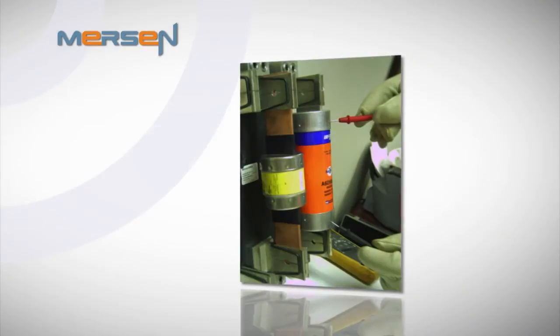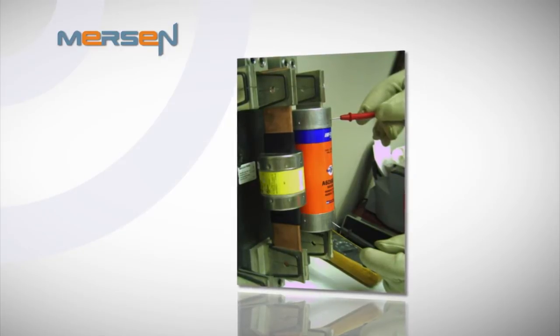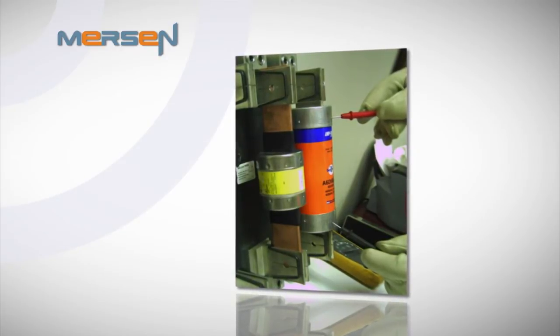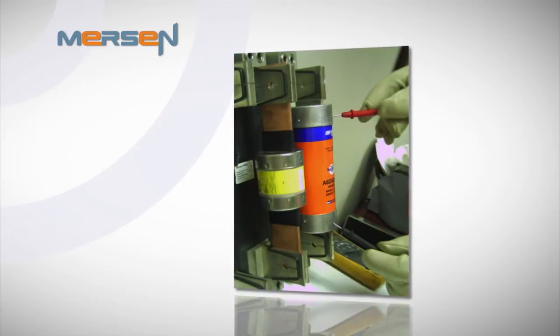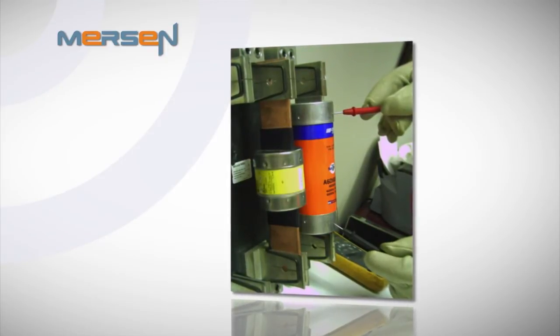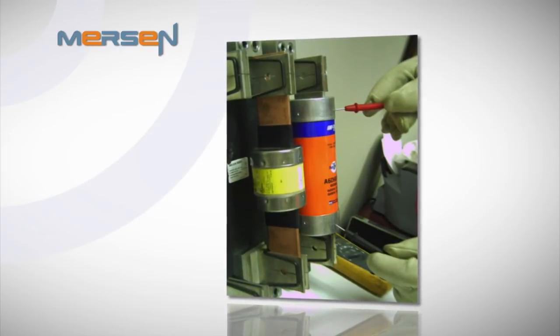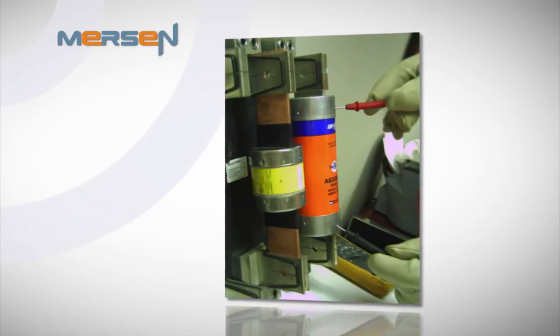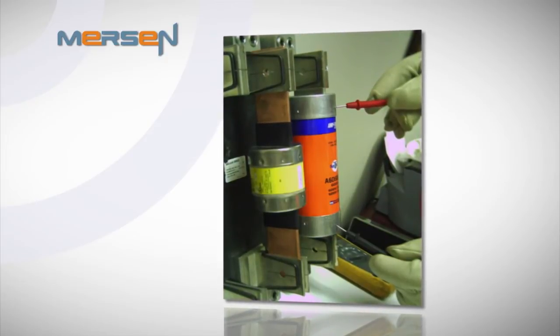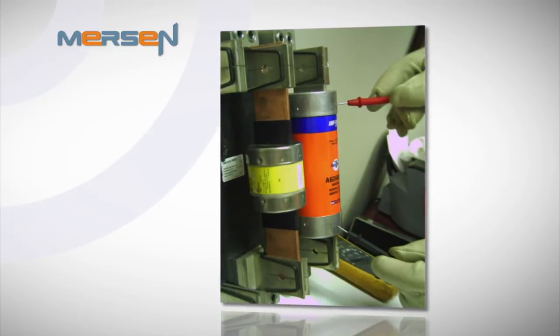An additional safety feature of Mersen's Amp-Trap 2000 fuses is the ability to test voltage with PPE to determine that they are safe. Mersen's test method keeps your people, plant, and equipment safe. OSHA requires lockout-tagout procedures that include testing for the absence of circuit voltage. Historically, people have used the fuse end caps for a convenient test location. Fuses with disconnected and insulated end caps can appear to be de-energized when they are not. As an industry leader, Mersen continues to provide electrical contact between the fuse element and the end caps to maintain customer safety.